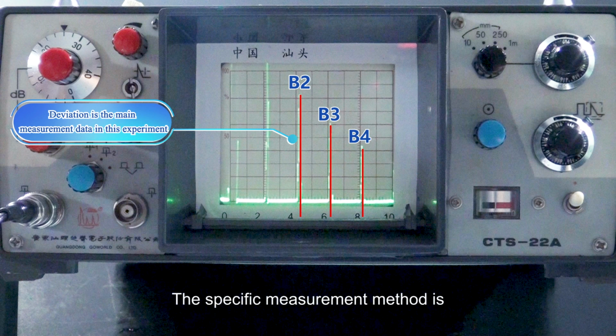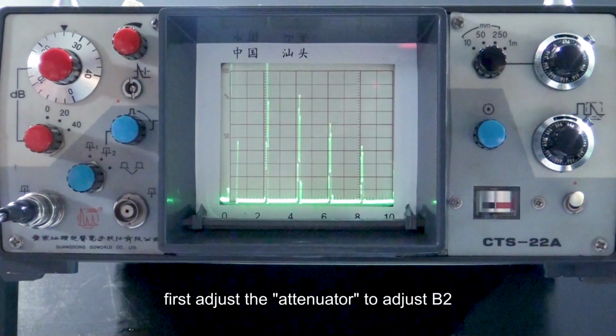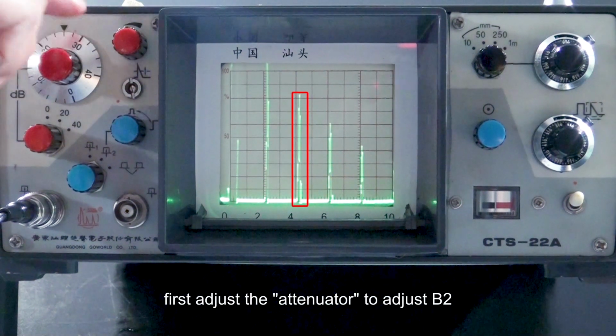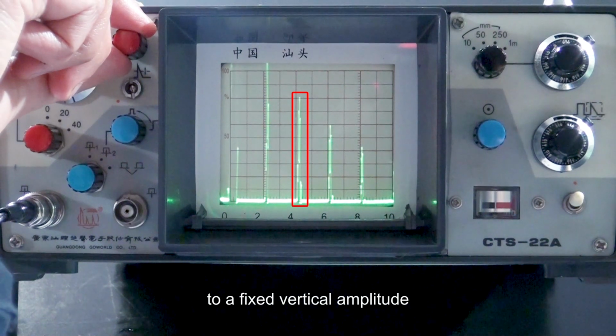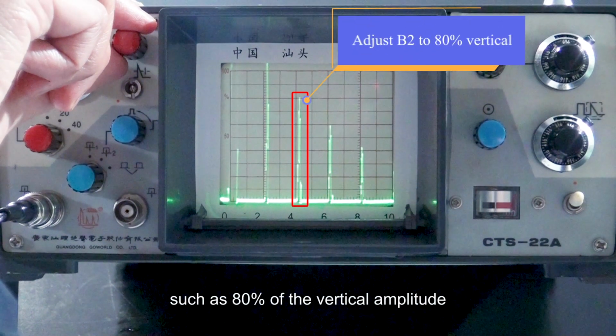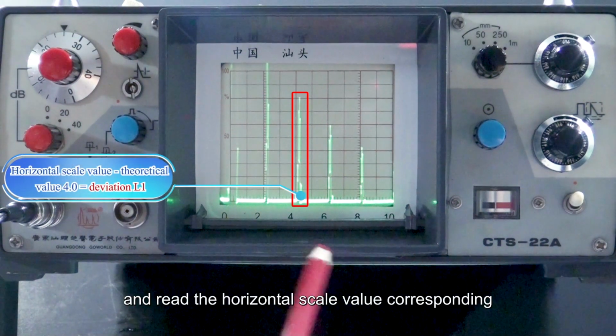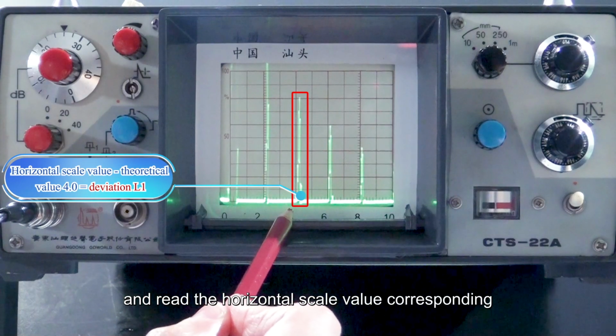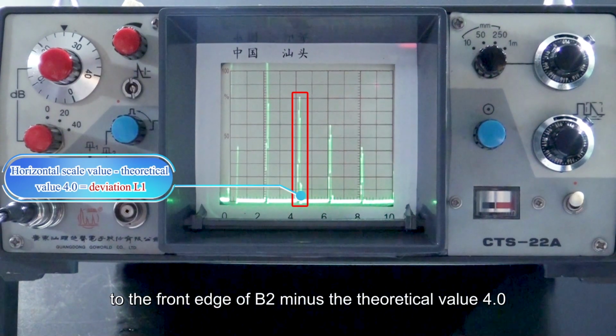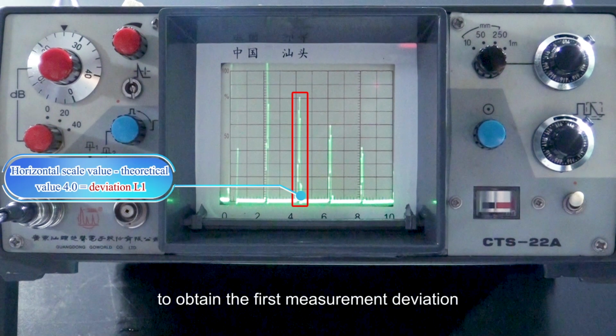The specific measurement method is: first, adjust the attenuator to adjust B2 to a fixed vertical amplitude, such as 80% of the vertical amplitude, and read the horizontal scale value corresponding to the front edge of B2 minus the theoretical value 4.0 to obtain the first measurement deviation, which is recorded as L1.